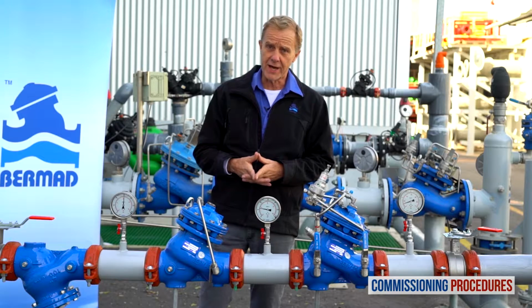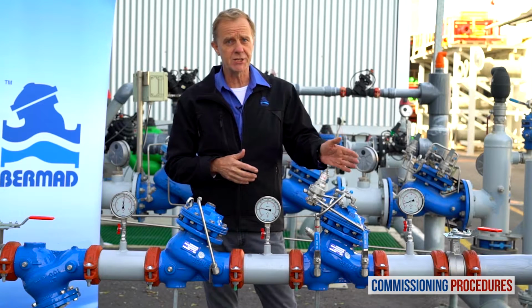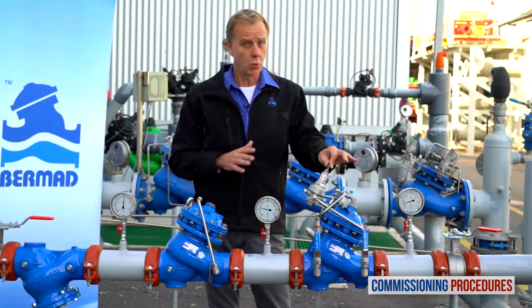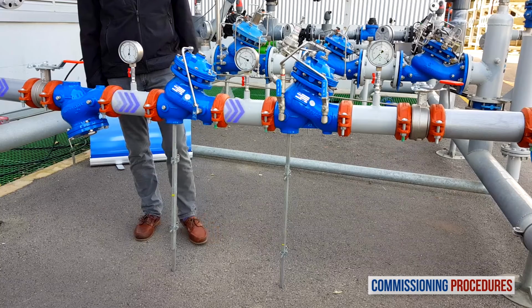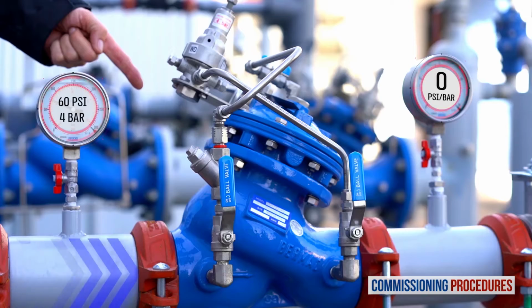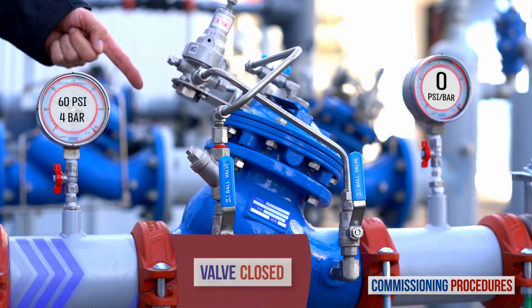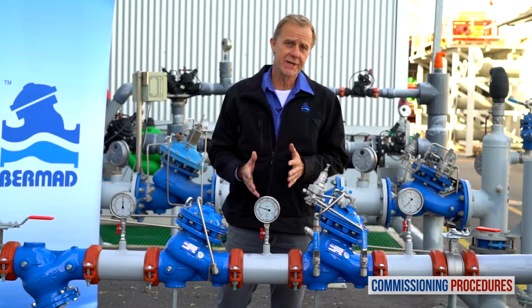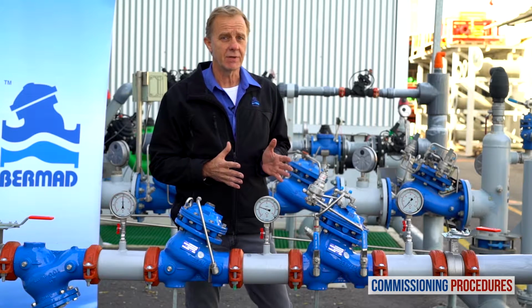On the other hand, if you did release the pilot adjustment screw to calibrate the pressure, water won't flow through the station. The reason is that in this case, the secondary pressure reducing valve will have closed shortly after introducing water to the station. Now let's calibrate the downstream pressure to the desired level.